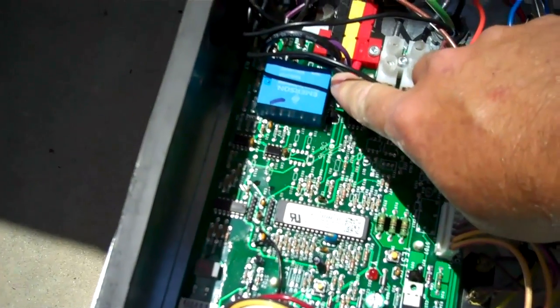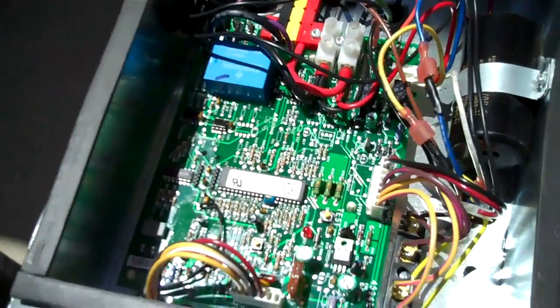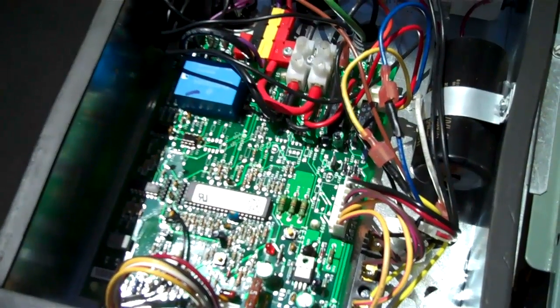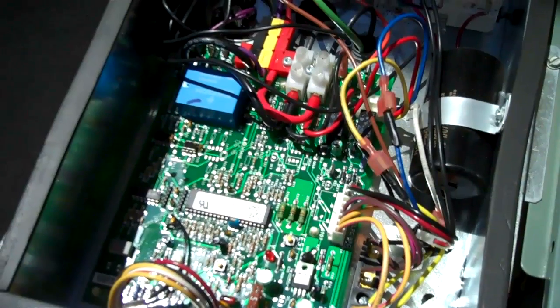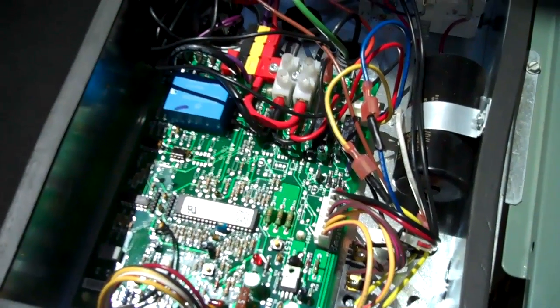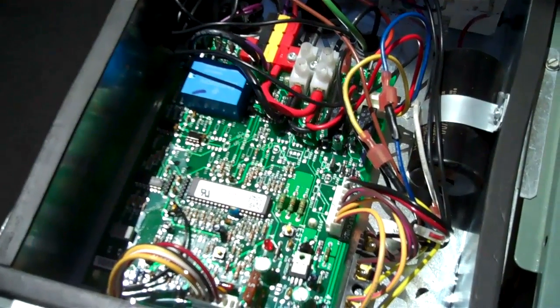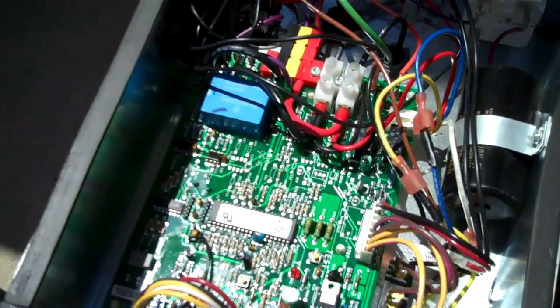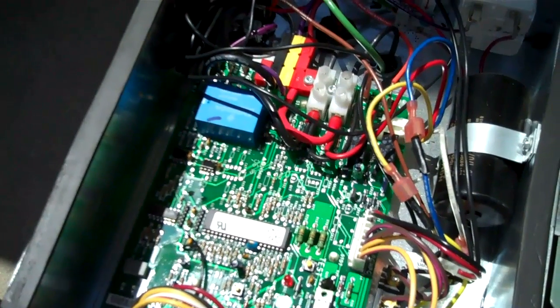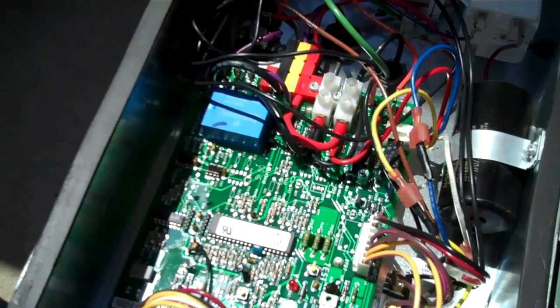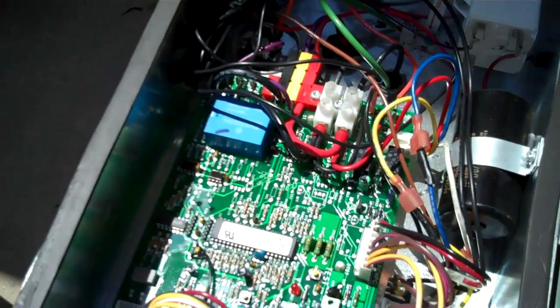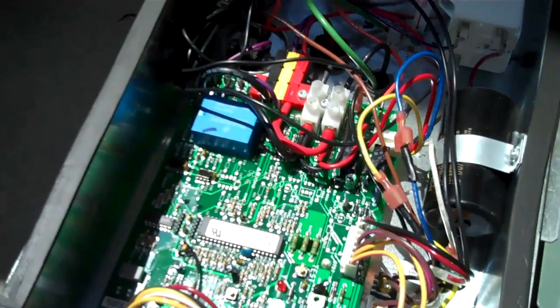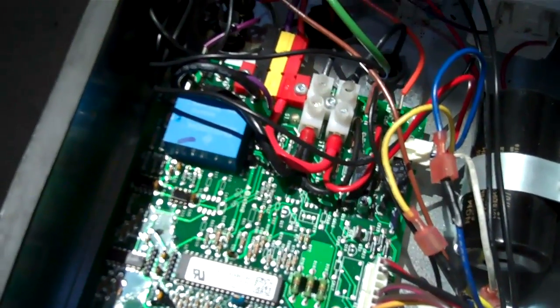Okay, this is the sealed compressor relay. It's an optical sensor, so it times the opening so that the contacts break when the voltage is at the zero volt level of the 60 hertz sine wave. So basically, when the unit's shutting off, it detects the light from the arc, and it's going to time it so it shuts down when the sine wave is at zero, so there's no volts, so you will not pit the contacts on that relay, and that's how they're able to put a relay in here instead of a real heavy duty contactor.